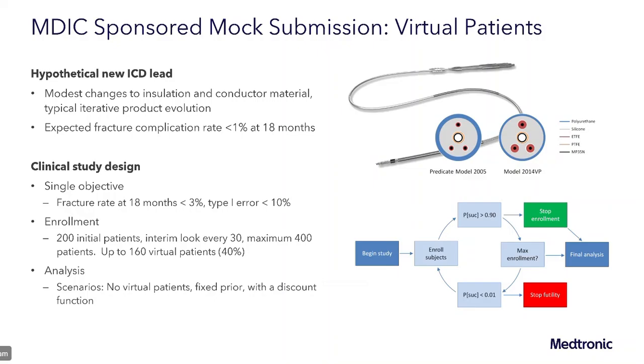Since this was specifically targeted at the use of engineering models in the submission, we didn't want to design a study here that would look at every single possible thing. We were really focused just on that safety objective for conductor fracture. We had a hypothetical fracture rate at 18 months that we'd expect to be less than 1%. We had performance criteria that it had to be better than 3%. And this is in line with what we'd seen for predicate studies.